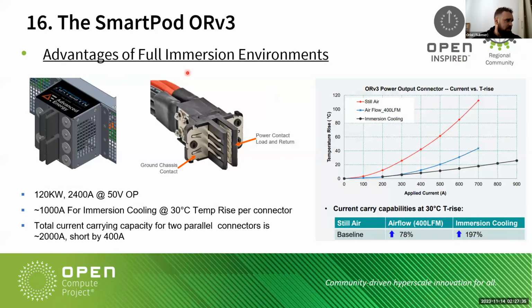Other advantages of full immersion environments are the connectors and bus bars, placed in the bottom of the tank. Comparing to air, we can bring 900 amps on a bus bar in immersion and connectors, and it will barely reach more than 23 to 25 Celsius. If we put just 700 amps in an air environment, we'll go over 110 Celsius on the connector or busbar, which is not very good. The immersion environment helps all components that get hot after receiving a lot of power or processing, making it a perfect place to immerse all of this.